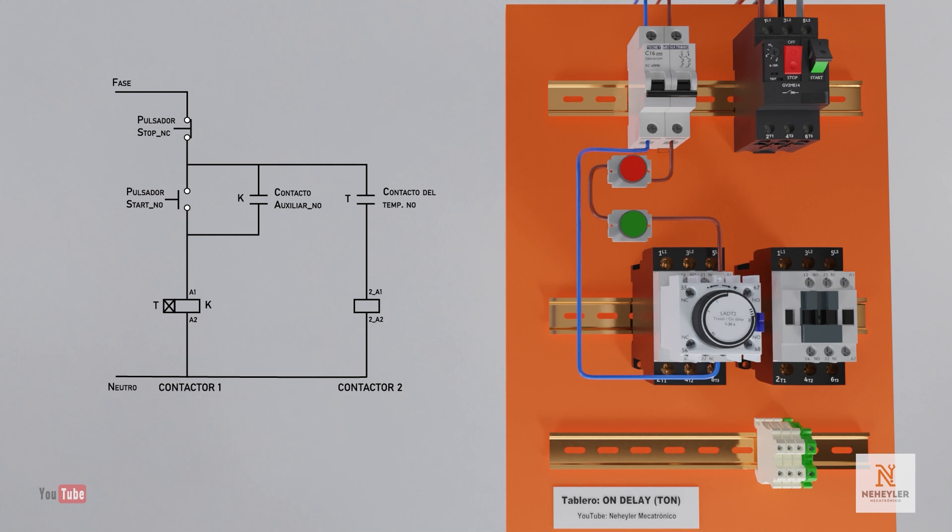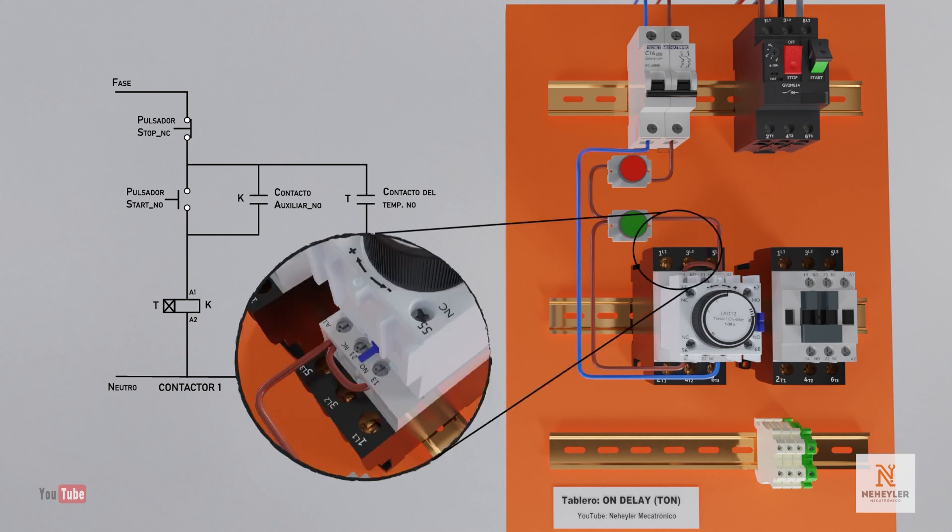Now, to make the contactor self-retaining and for its coil to remain energized, a cable must be connected in such a way that the normally open auxiliary contact 1314 is parallel to the start button.